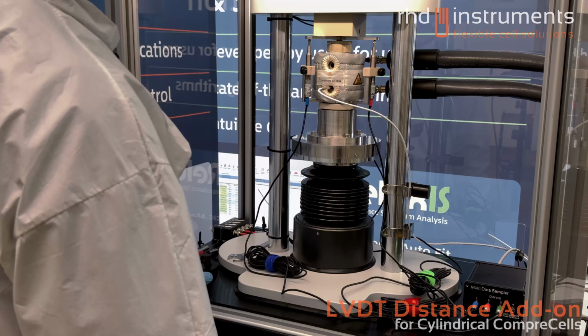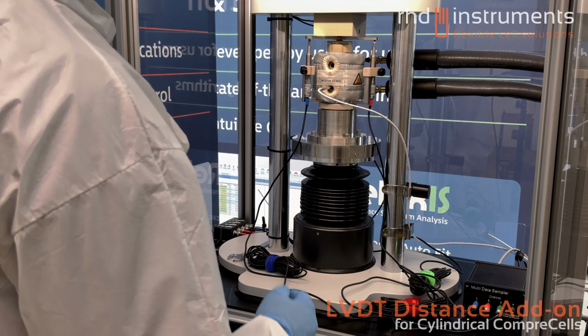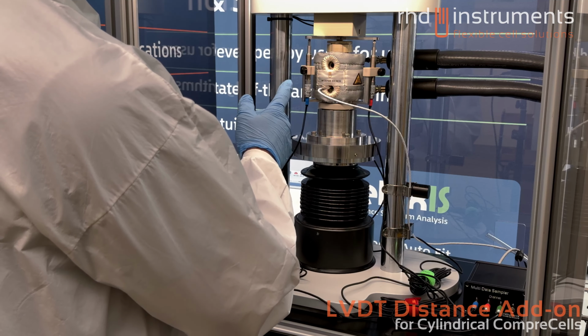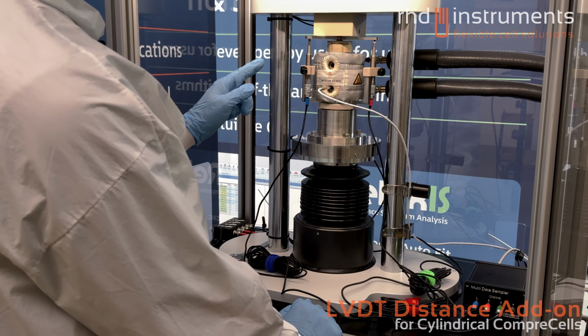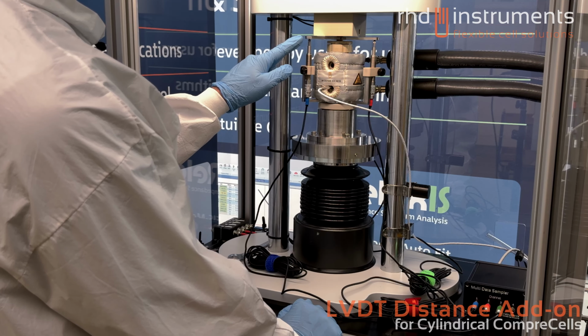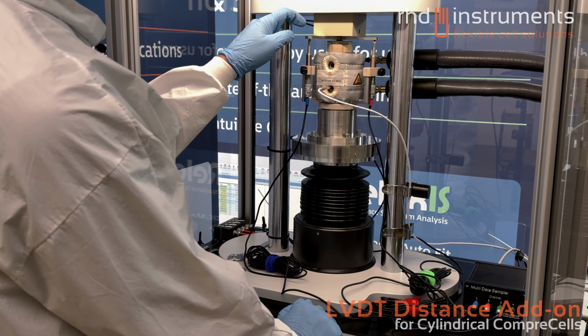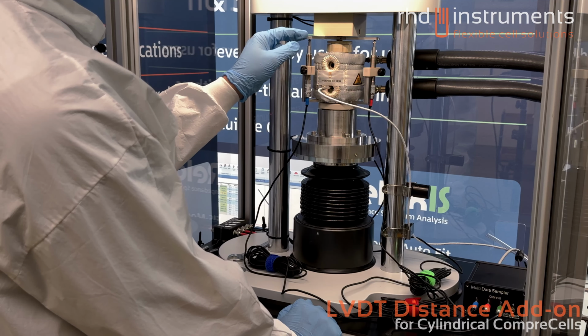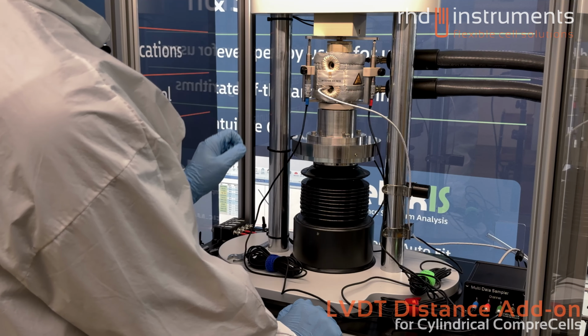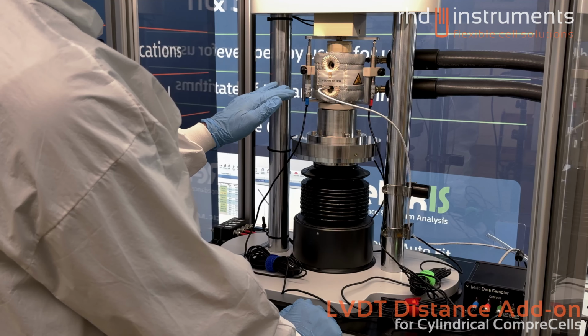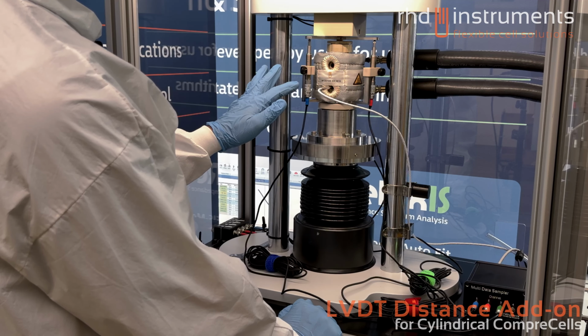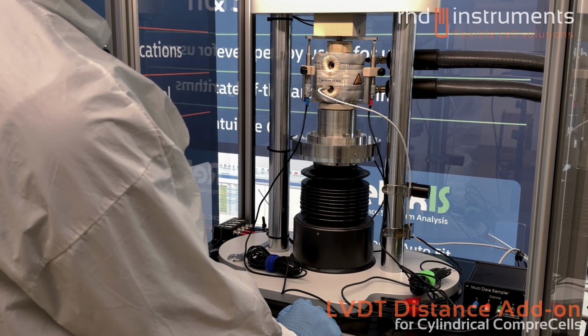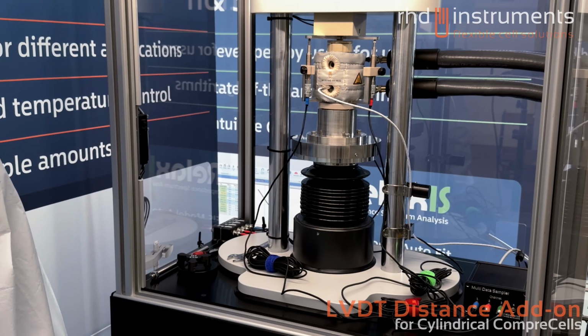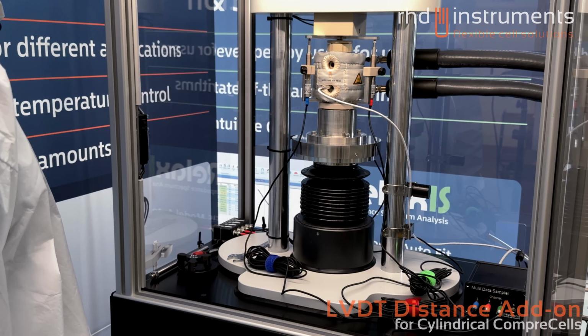Generally, please be aware that the sensors are grounded and make sure that the sensors do not touch the temperature probe or any parts of the cell holders. So for example, on the cantilever there is an insulated part in the middle where the probe is supposed to touch, but it's not supposed to touch any other parts of the cell. On the other hand, the bottom sensor holder metal parts should not be touched by the sensor. Now the LVDT distance add-on for cylindrical CompreCells is fully assembled.